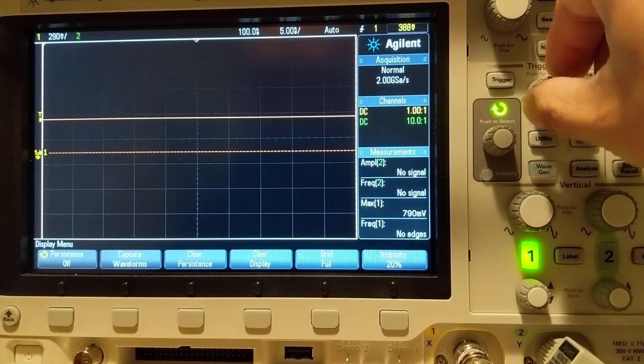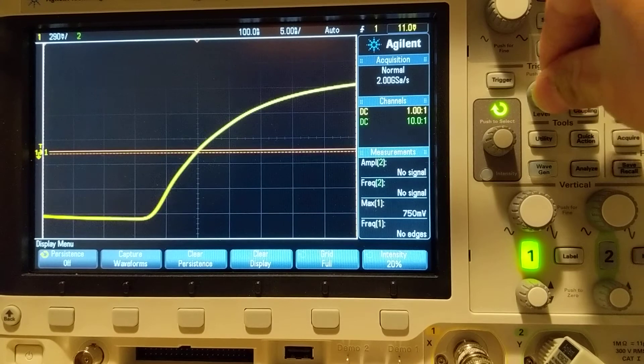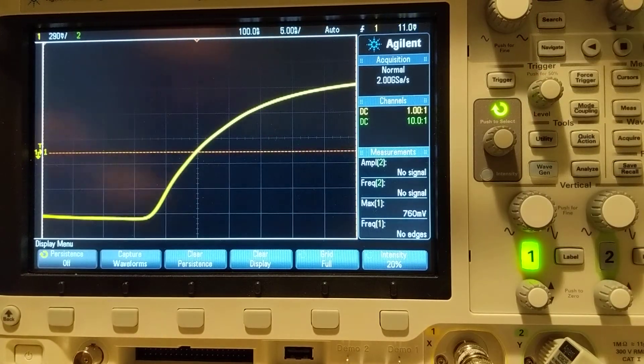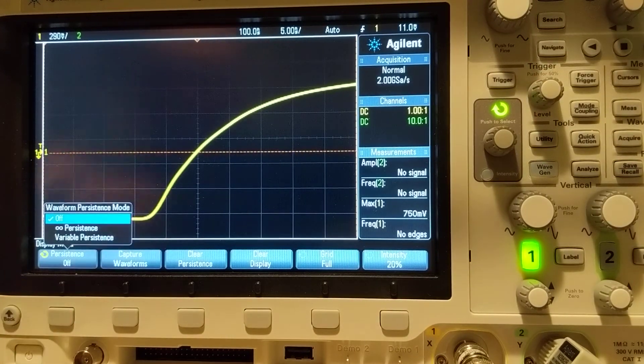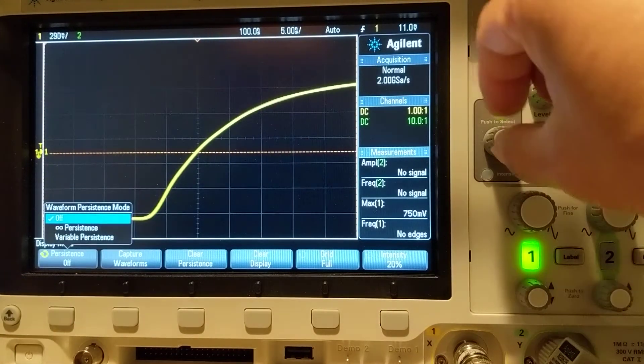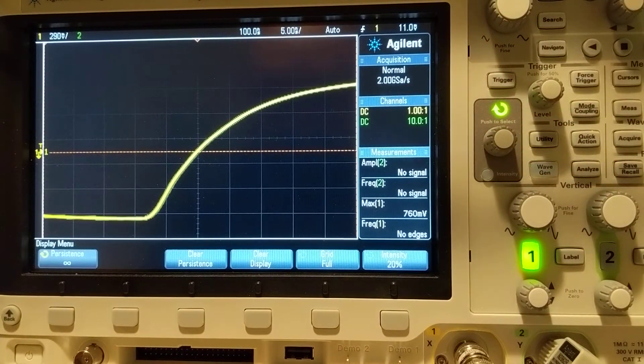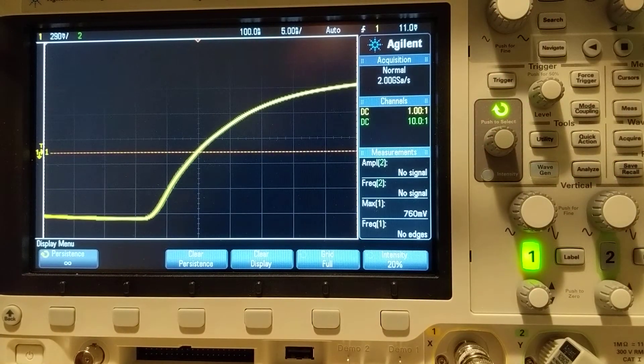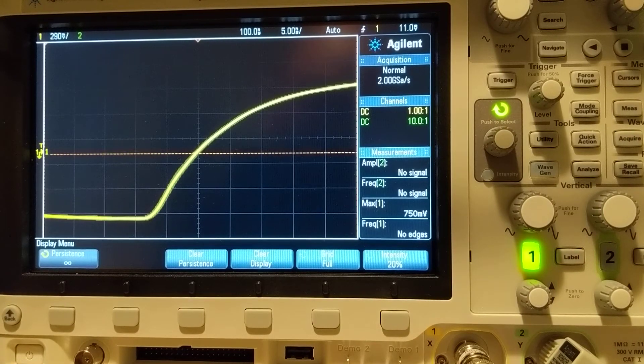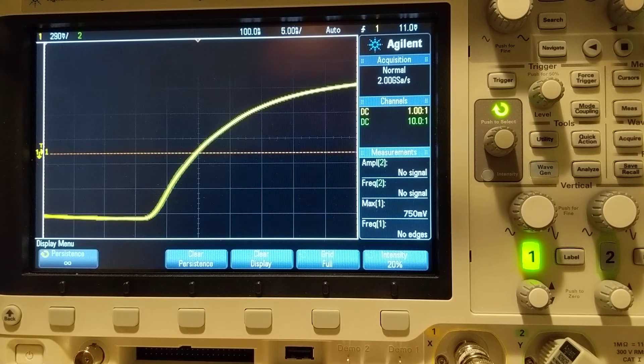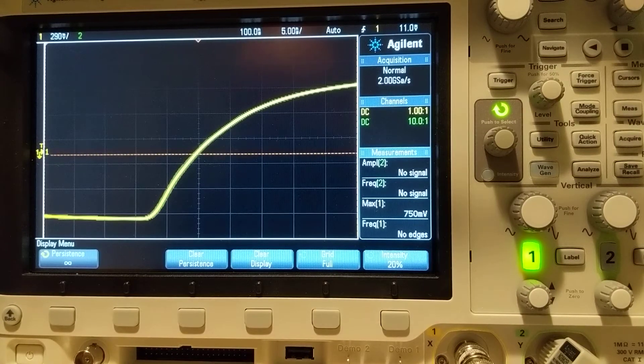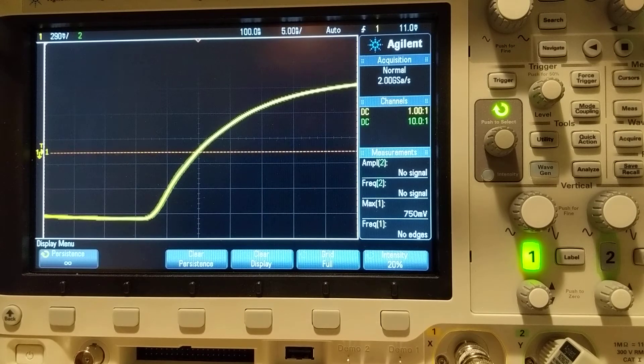Okay, sorry. Persistence is supposed to be infinity. Can you see the difference? Looks like a little bit wider, but still pretty good. So it proves that this clock source is very good.